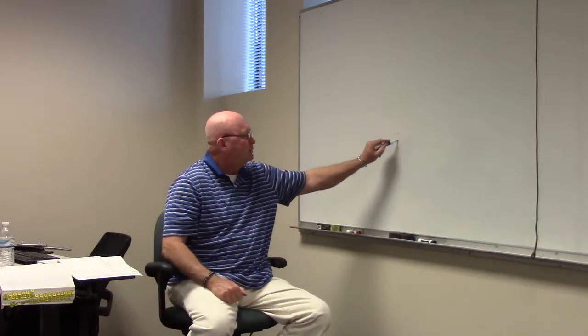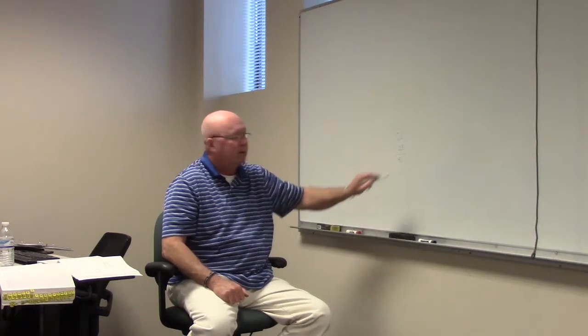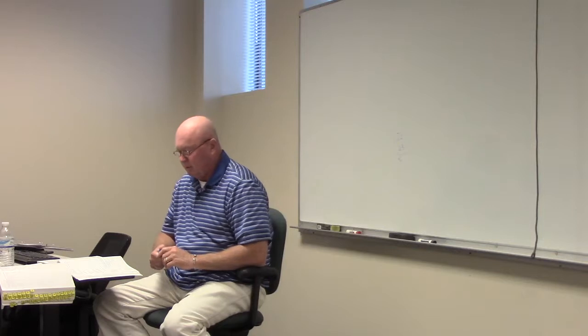And that would be the 20 amp motor, because we had two motors. We had a 20 amp, we had a 16.7. So we're taking 25% of the 20 amp motor, and so 20 amps times 0.25 is what? It's 5, isn't it? As you can see there, note E, we've added 5 amps to our load.